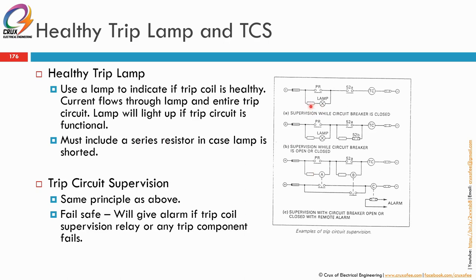Okay. So one purpose is to protect from mild nuisance if this lamp is shorted. Another is to limit the current flowing. Maybe to light up the lamp you need only 0.01 amp, but the trip coil needs 0.1 amp. So without this resistor, you can trigger this trip coil to trip through this circuit. Okay, so the resistor must be there. So this is while the breaker is closed.